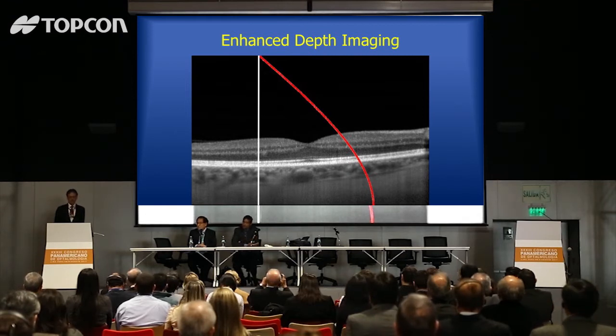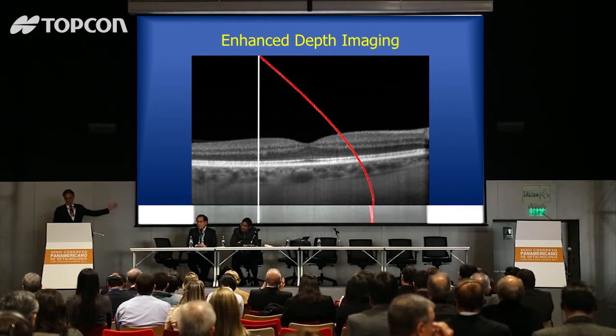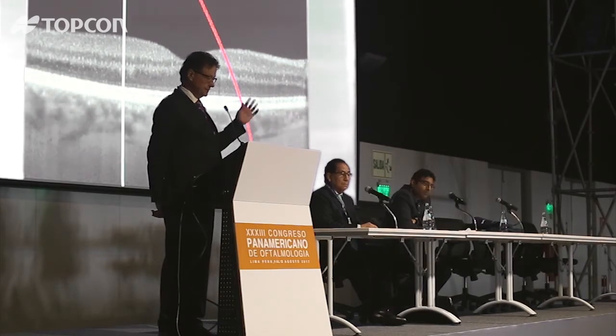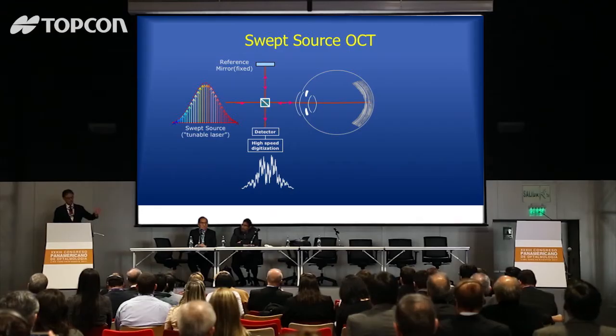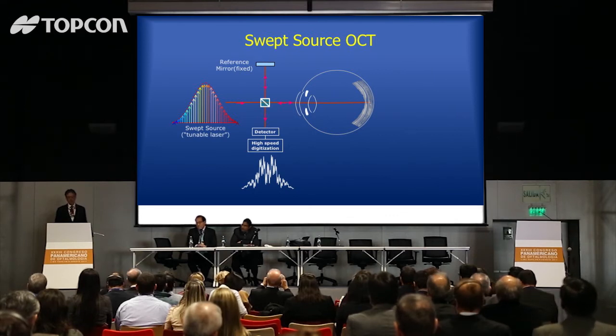With spectral domain OCT, we have to make a choice: we either look at the vitreous and retina, or we look at the choroid. We can't easily look at both simultaneously. With swept source OCT, individual wavelengths are sent into the eye sequentially, making an interferogram detected by a photodiode — a much faster detection method. The interferogram is built up and decoded by the same Fourier transform idea to make an A-scan.